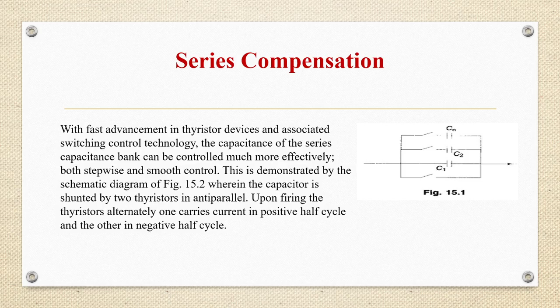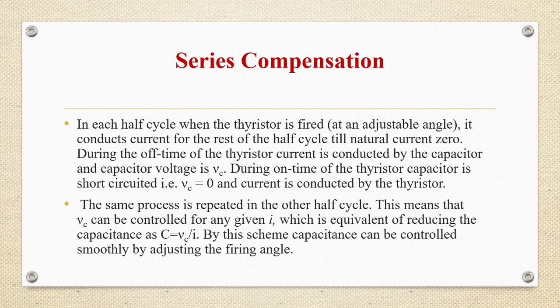Upon firing the thyristors alternately, one carries current in the positive half cycle and another carries the current in the negative half cycle. In each half cycle, when the thyristor is fired at an adjustable angle, it will conduct current for the rest of the half cycle till the natural current zero. During the off time of the thyristor, current is conducted by the capacitor and the capacitor voltage is Vc. During on time of the thyristor, the capacitor is short circuited, that is Vc is equal to 0, and current is conducted by the thyristor. The same process is repeated in the other half cycle also. This means that Vc can be controlled for any given current I, which is equivalent to reducing the capacitance C, since C is related to Vc by I. So by this scheme, capacitance can be controlled smoothly by adjusting the firing angle.